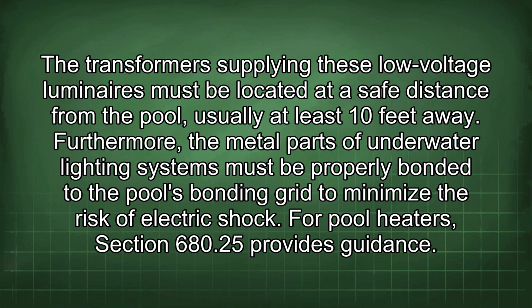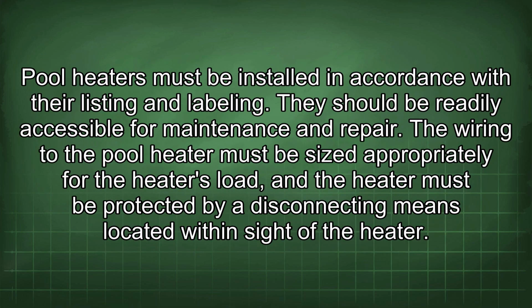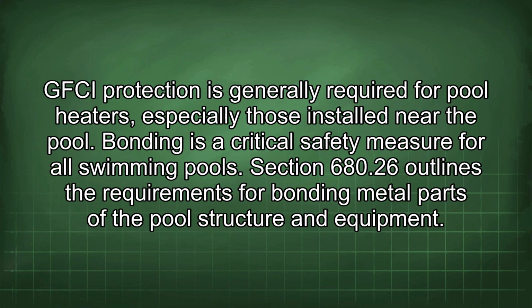For pool heaters, Section 680.25 provides guidance. Pool heaters must be installed in accordance with their listing and labeling. They should be readily accessible for maintenance and repair. The wiring to the pool heater must be sized appropriately for the heater's load, and the heater must be protected by a disconnecting means located within sight of the heater. GFCI protection is generally required for pool heaters, especially those installed near the pool.